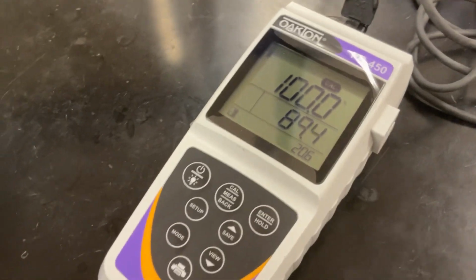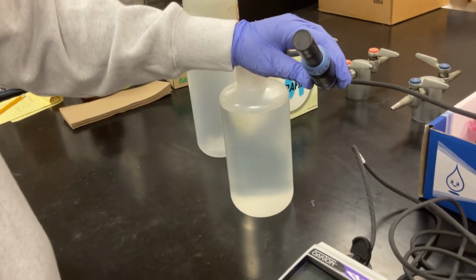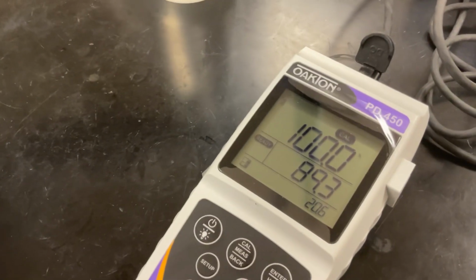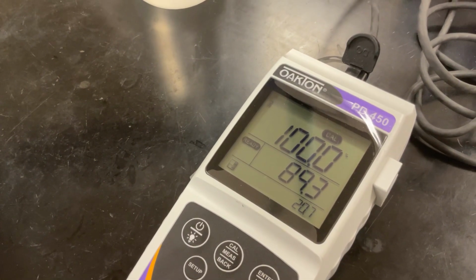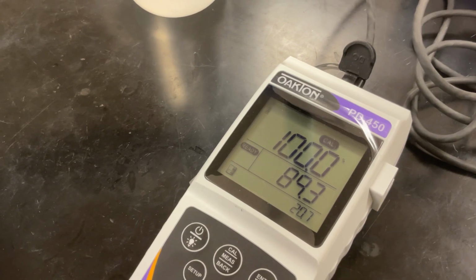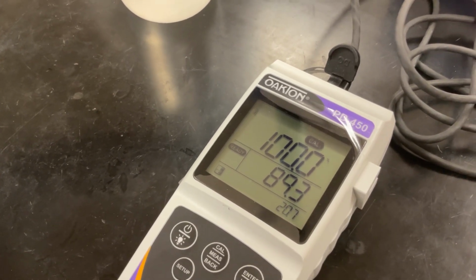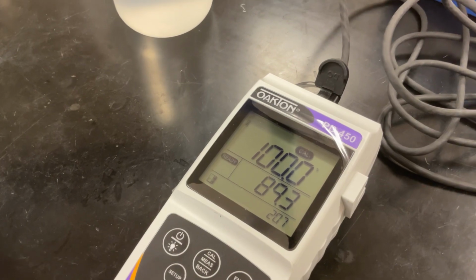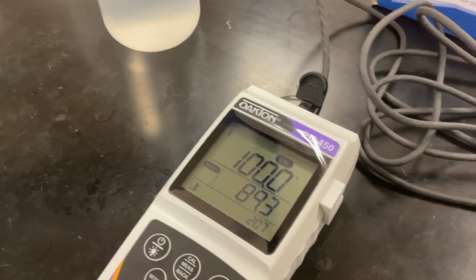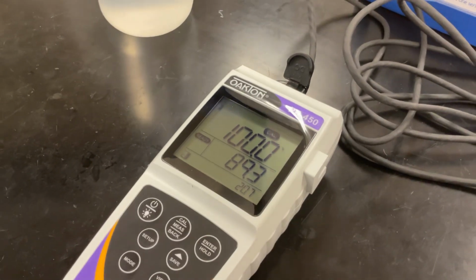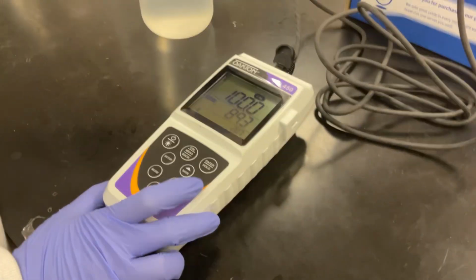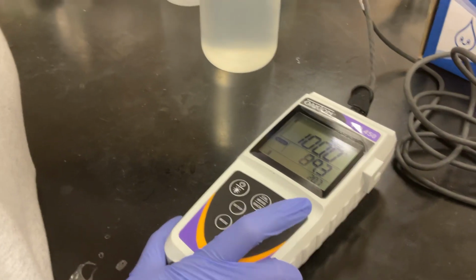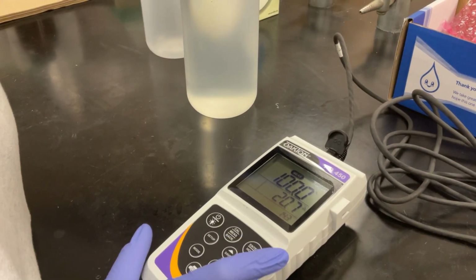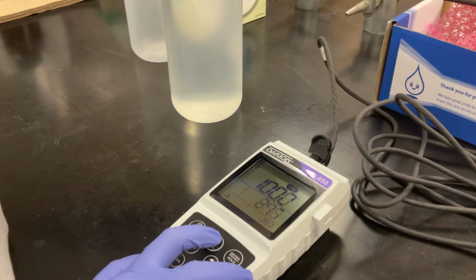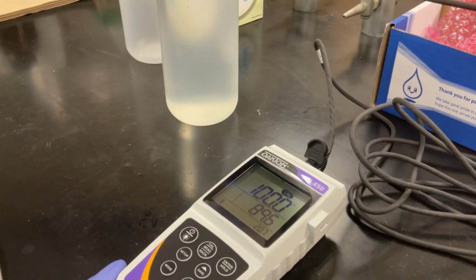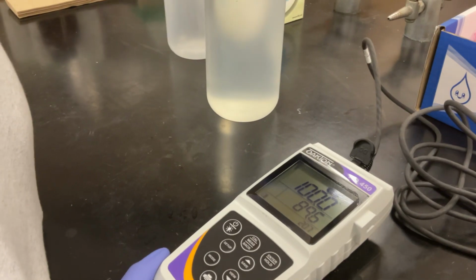And here we are holding the probe up in the atmospheric oxygen and calibrating at 100%. And it says 89.3 and it's ready. So here's our problem. We can't get it to change to 0, so we can do a 0% calibration with the sodium sulfite. And so you're supposed to hit enter, done, go to calibrate, and I mean, there's just no way to change it to 0.